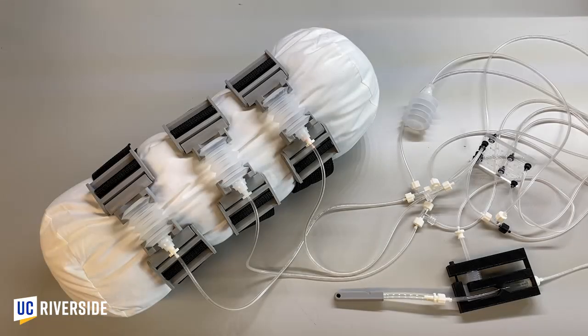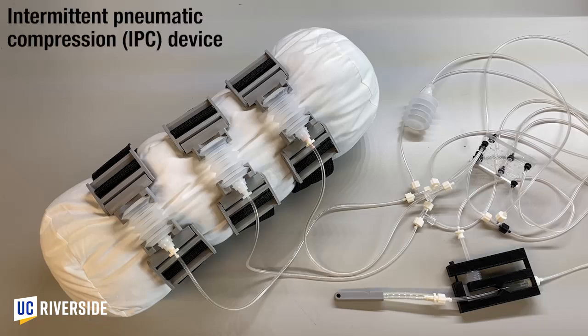In this video, we use our pneumatic error detector to sense problems in the operation of a model medical device, an intermittent pneumatic compression or IPC device.